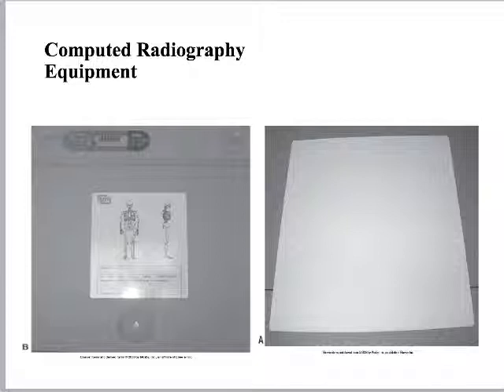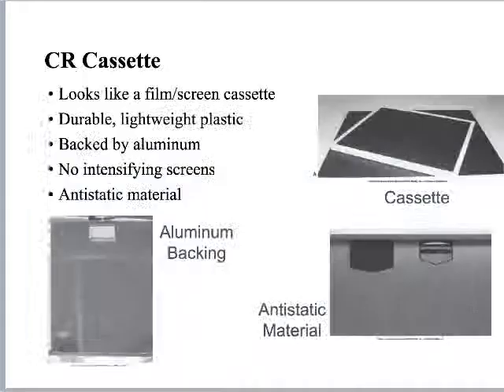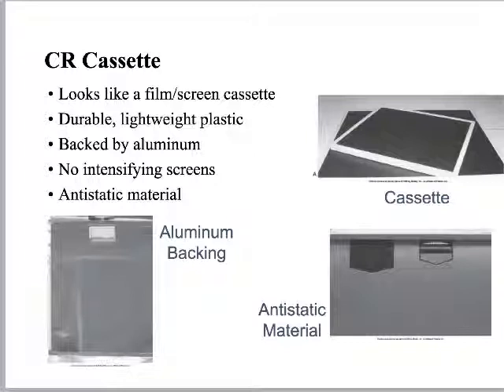The phosphor plate is responsible for capturing x-rays as they exit the patient. The CR cassette is typically fairly durable, made of plastic and lightweight, with an aluminum backing to catch any x-rays exiting the cassette. They do not have intensifying screens, but they do have anti-static material inside. As the PSP plate is pulled out by the reader, if there were static, it would create an artifact. So we do not want any static as the PSP plate is pulled out.